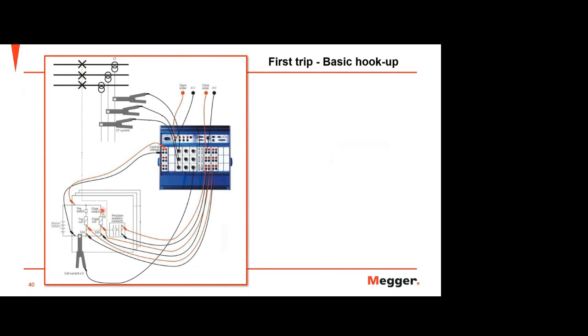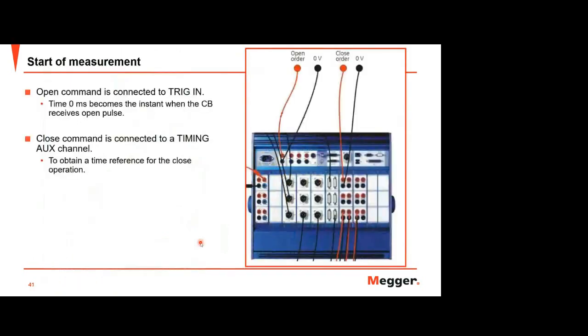But this connection means you can still access it when the system is online, because we touch the LV side of the system. We don't touch the high voltage side of your system. So you still can do it. And for this command, we just need the command from external. Either you can press it manually, or you can do it remotely through the control room. And you just make sure you can see the waiting trigger, meaning the instrument here is ready to get the trigger or to get the measurement.